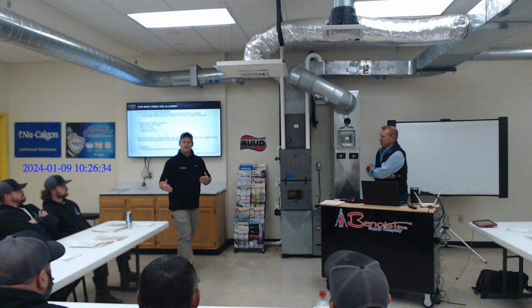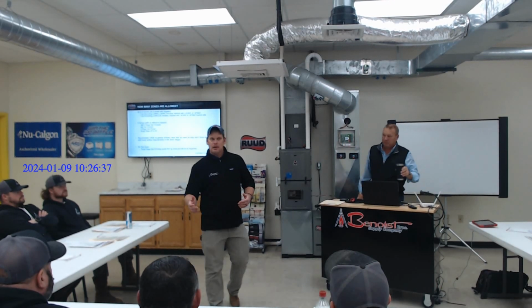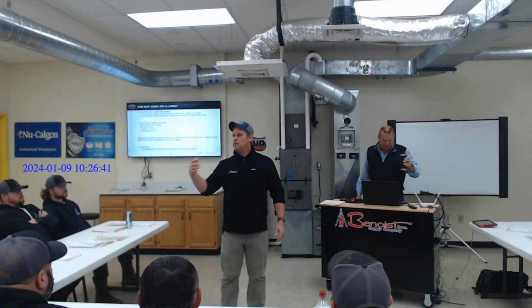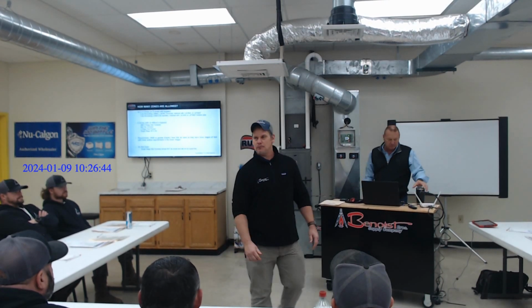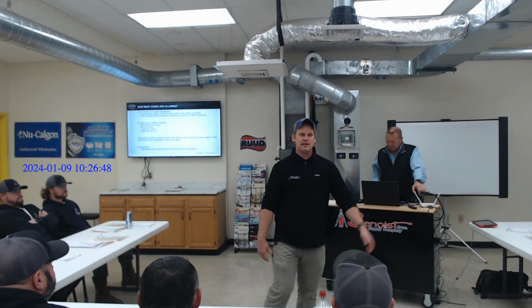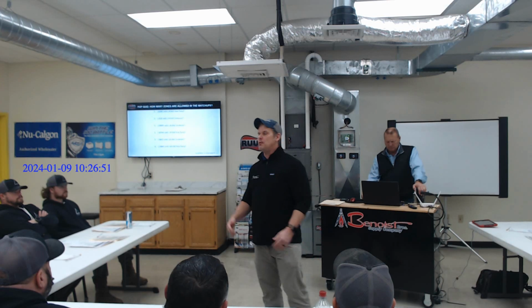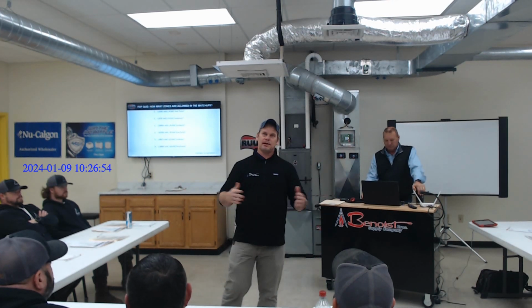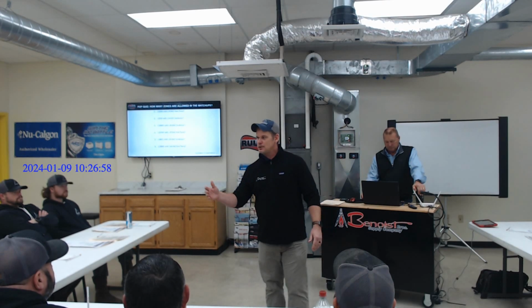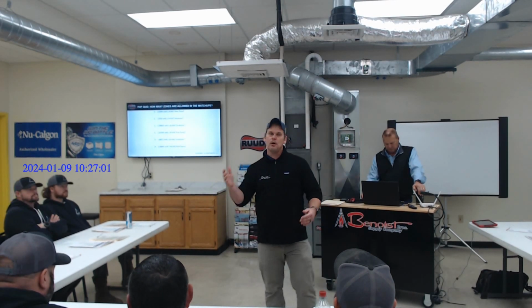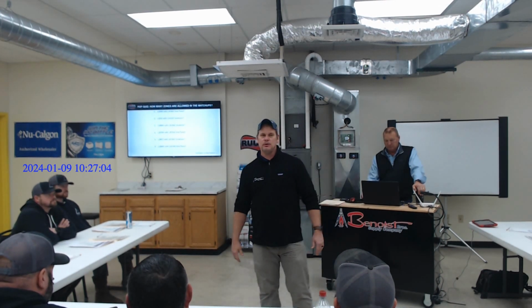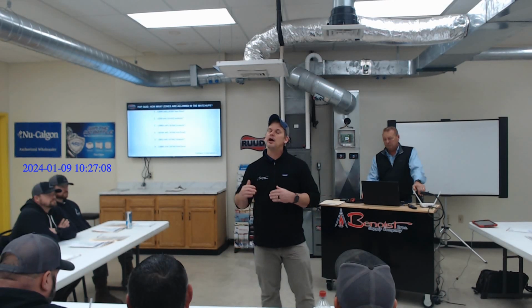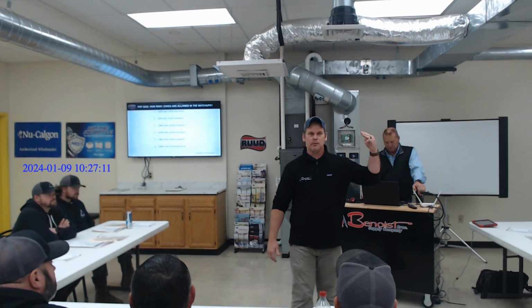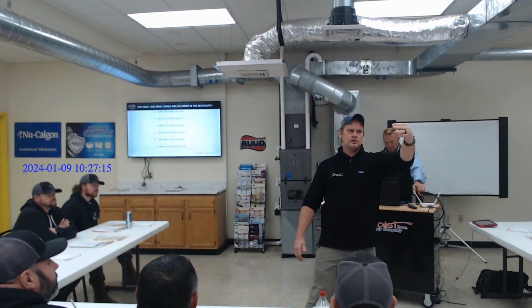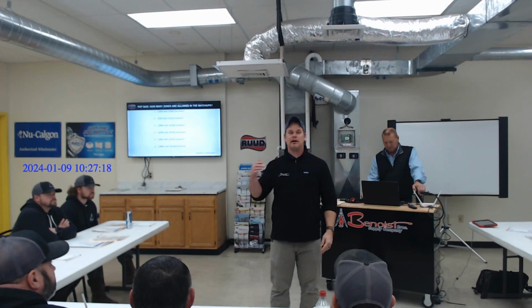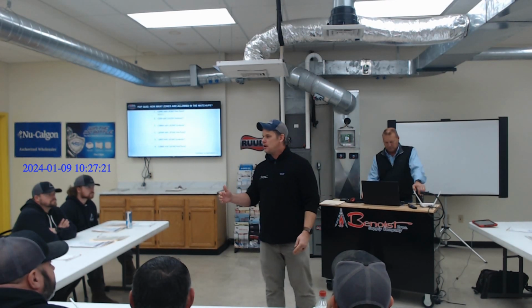So let's bring it back. I can see the wheels turning. I can see questions being asked without being asked. We did a heat load. We're going into this house. It's always had a 3-ton, it's always had a 4-ton. Heat load requires that: the windows, the ceilings, whatever. So we've done our heat load calcs, and that's great on new construction because we can design our ductwork for that heat load, right? But a lot of you guys are going into retrofit. All right, you're putting our ECONET zone on old ductwork. Well, it needs 3 tons of cooling. Fine, we understand it needs 3 tons of cooling. Your ductwork cannot handle it. So no longer can we go in with the famous 3 fingers. That house is 1, 2, 3 tons, right? Now, because of these motors, what Dave's getting to, we have to look at our ductwork first and foremost.